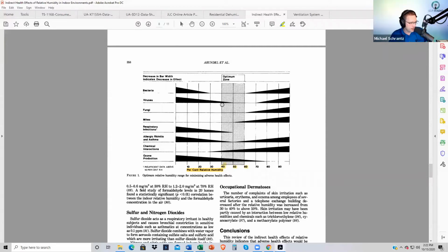Yeah, I did a recent podcast with a clinician who was asking questions about ventilation and filtration requirements based on COVID thoughts. It was tricky to navigate because if you don't consider confounding issues, say you bring in more mechanical ventilation, now you dump a bunch of moisture-laden air in the house. Or you stick a higher MERV rated filter on an old system that can't handle the resistance, and now you have a condensation leak in the summertime or a frozen coil, and the list goes on.